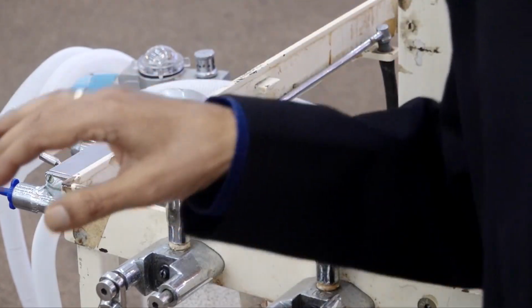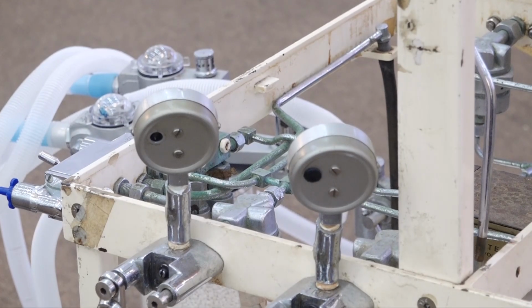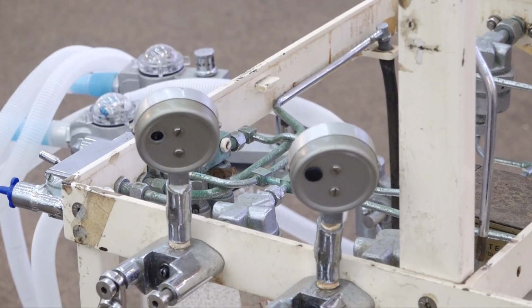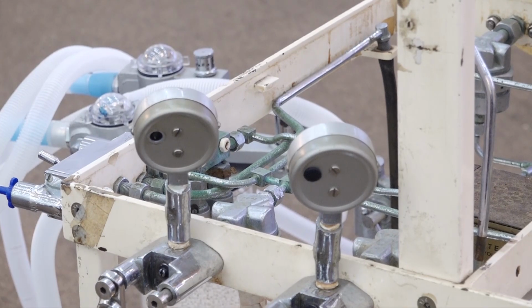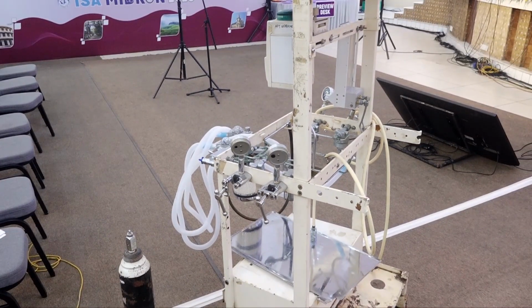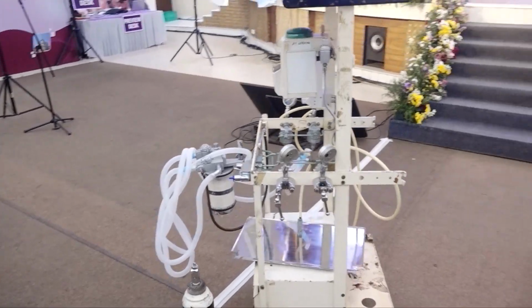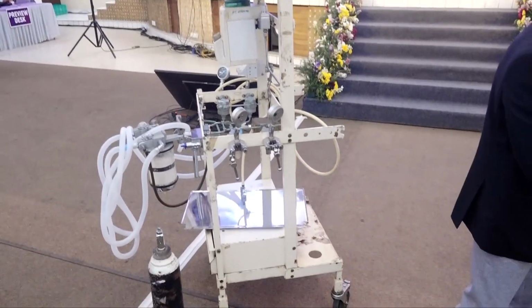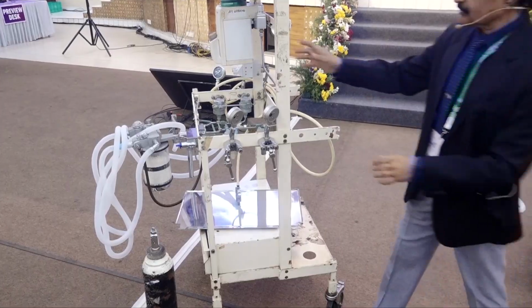So that is the reason this is one of the safety features. Just remember about this also, the safety feature that has been adopted. In the most modern workstations, where everything is electronic equipment, you have electronic pressure transducers. These will give the pressures of the pipelines as well as the cylinders on the information screen itself. Once you open it, you can see the pressures continuously shown on the information screen in the most modern electronically controlled pressure transducers.